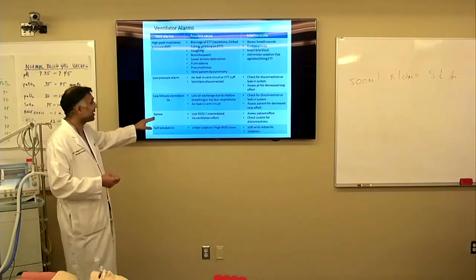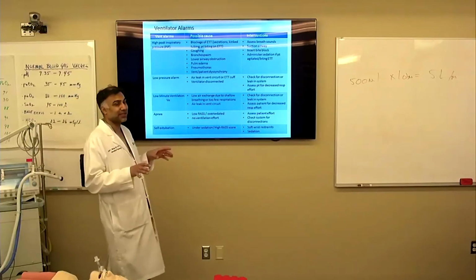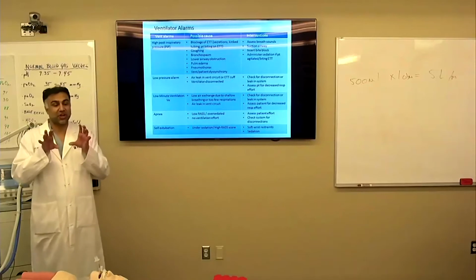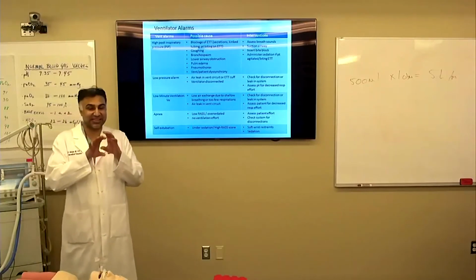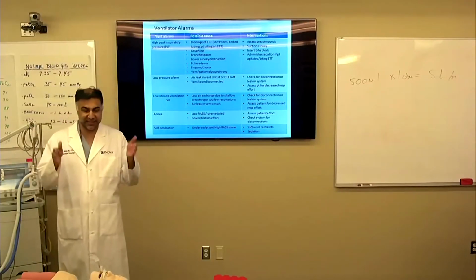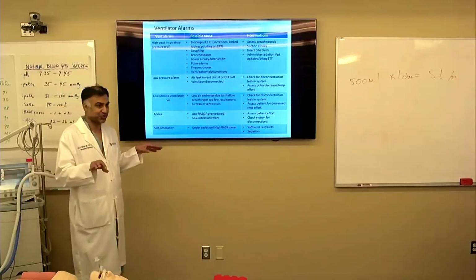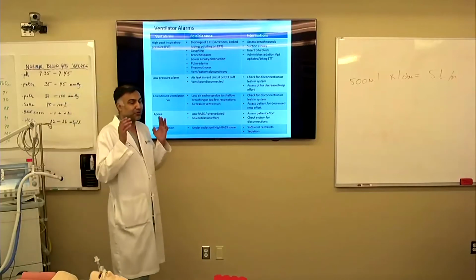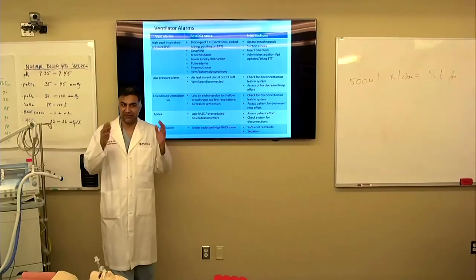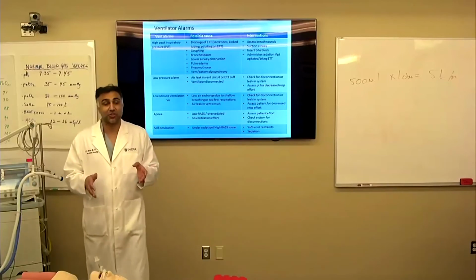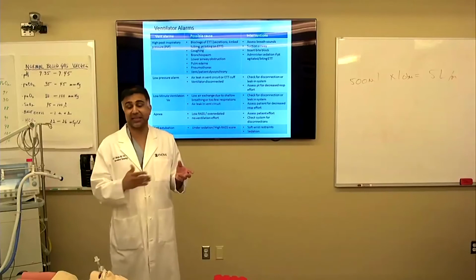When we talk about apnea, it's important, mainly because no matter what you do, the ventilator itself is set to deliver a certain number of breaths every minute, even if the patient doesn't trigger the ventilator. Meaning that if you put in that you want 10 breaths a minute, every 6 seconds is going to be a breath. So if the patient doesn't trigger it, it automatically gives it every 6 seconds.